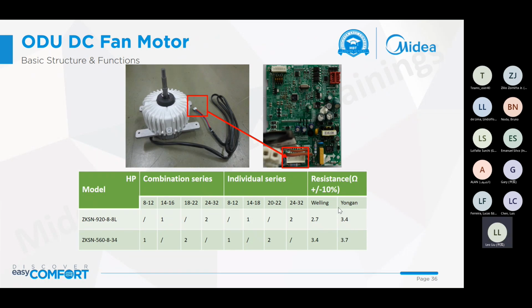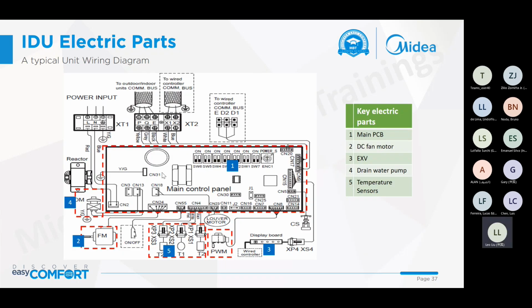Yong'an brand is a little bigger. And this is the connection for the DC fan motor. We connect to the DC fan driver board. We use two models of the DC fan motor for the full range of the unit. The biggest size we use is the 920 model.